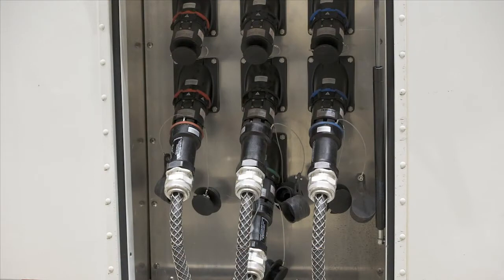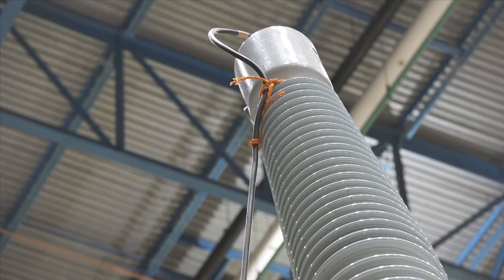Connect the power cables to the power supply. For high currents greater than 100 amperes, bolts instead of clamps should be used. Make sure that the bolts are properly tightened. Apply appropriate markings so that personnel do not accidentally get close to the transformer and its connections. The power cables should be connected between the converter and the high voltage bushings. For transformers with a high current rating, 2 cables have to be connected in parallel, 2 × 120 mm squared.